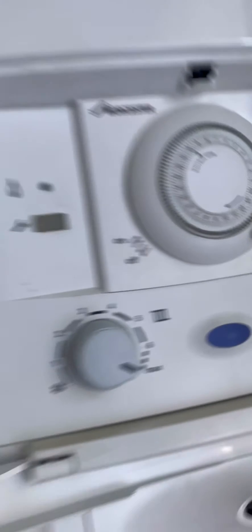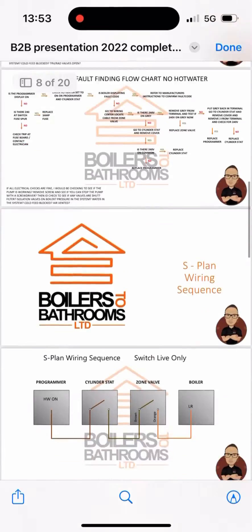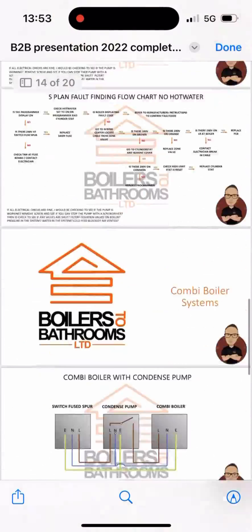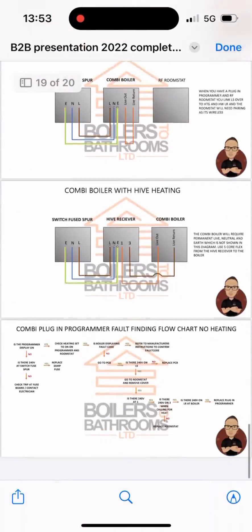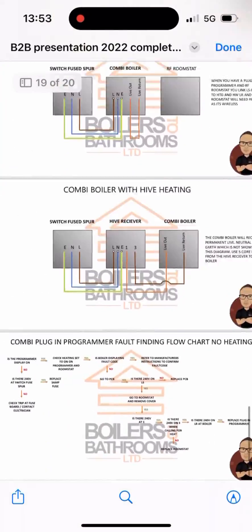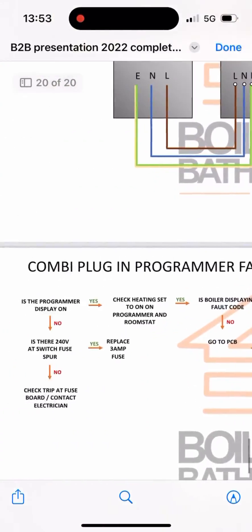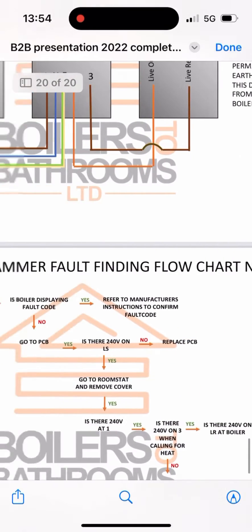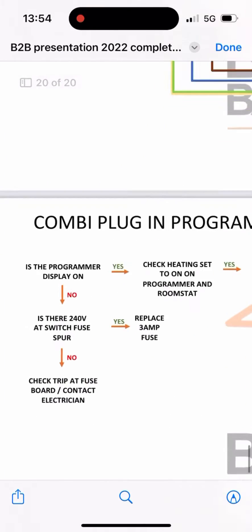We've turned up to a no heating fault on a combi boiler with a plug-in programmer. Whip out the breakdown bible, scroll all the way down to combi systems. At the bottom there's a combi plug-in programmer fault finding flow chart for no heating.